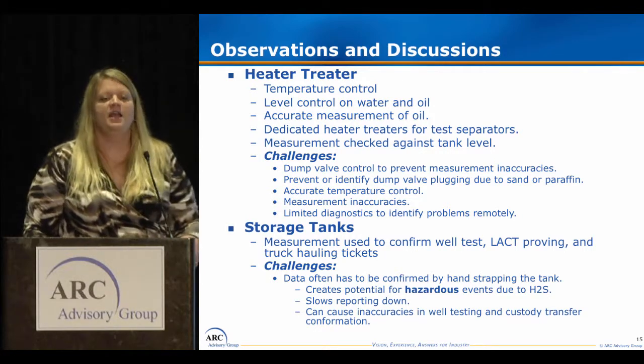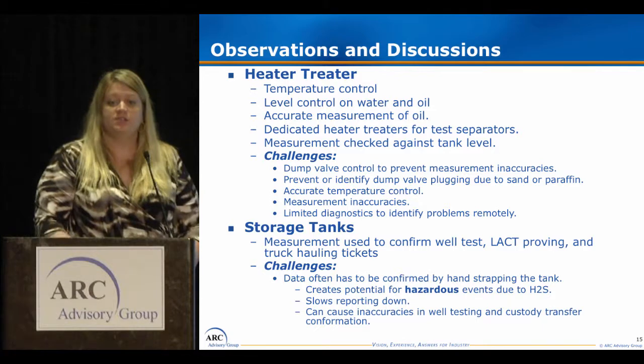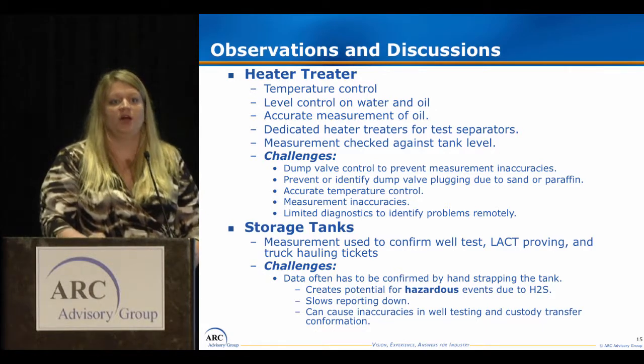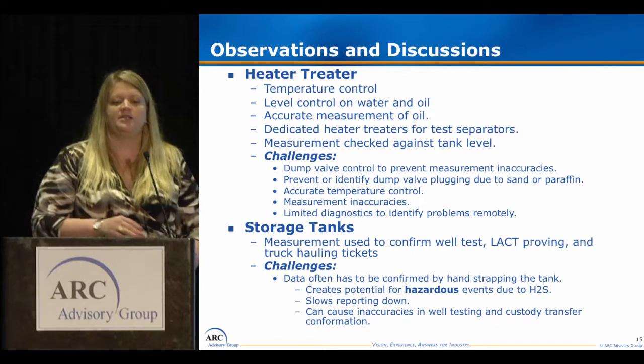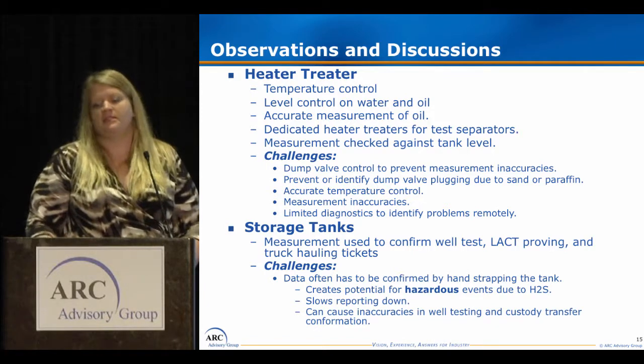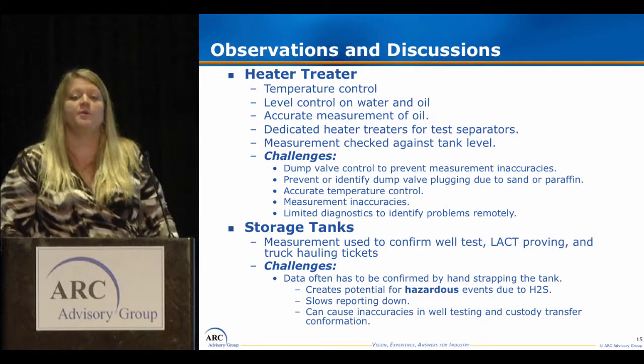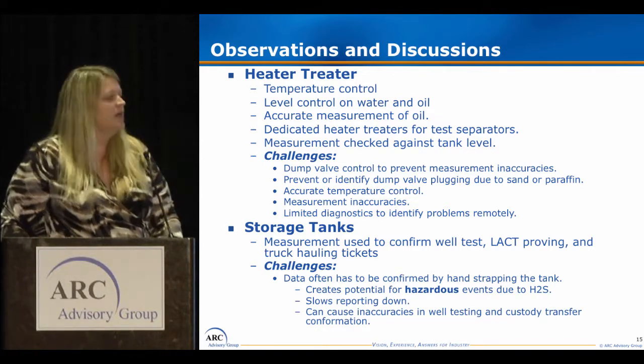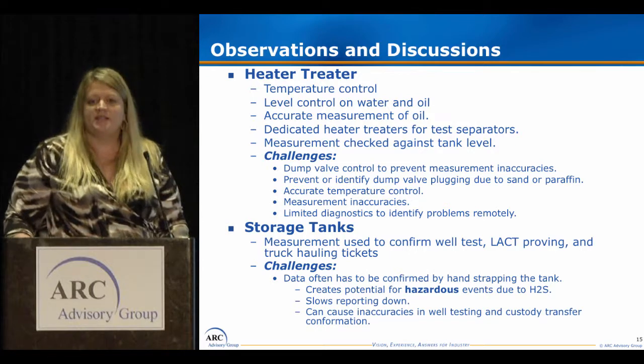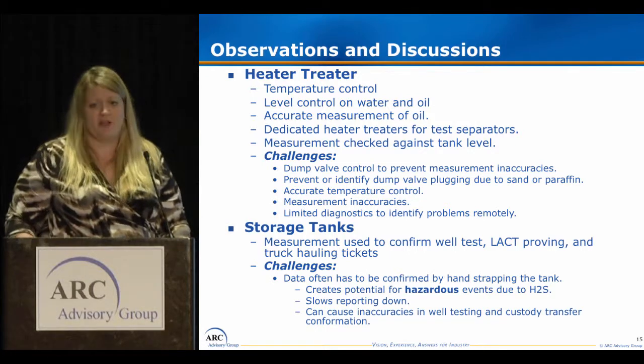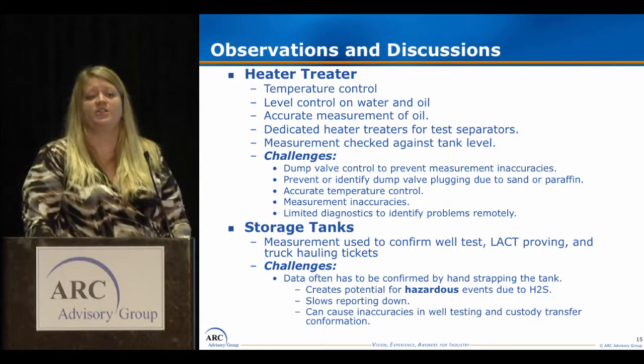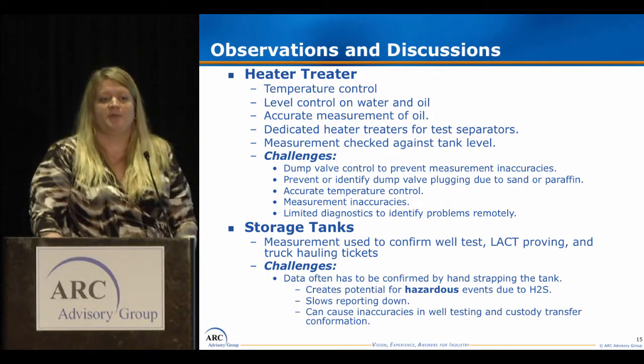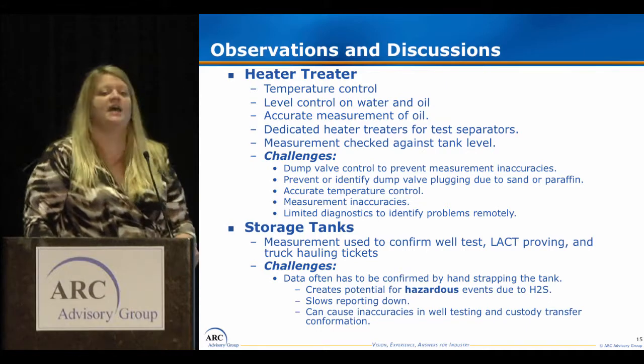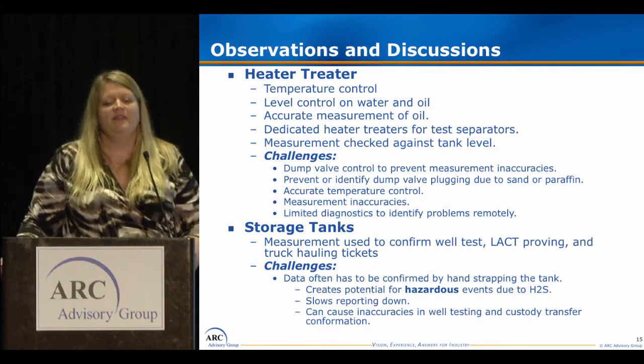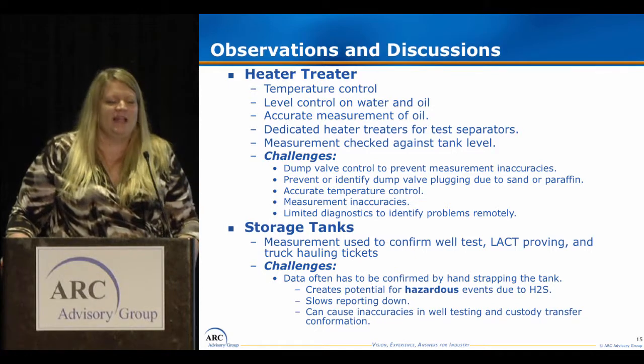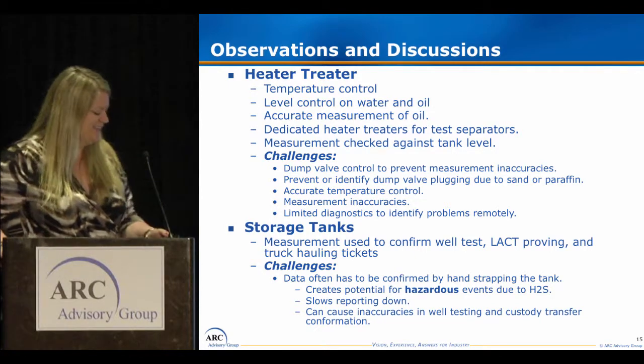A big thing, and the first thing I focused on, was gauging the tanks. I don't want any manned personnel manually gauging tanks, because in Eagle Ford we have high H2S. In Mississippi it's not so much a problem, but we're pretty remote, and you're out there by yourself. So unless something is wrong with the SCADA equipment or RTU, which is very unlikely, the RTU data is still there, and they don't need to be on top of the tanks gauging. That was a pretty easy transition, and they were mostly thankful, though I guess they did like climbing up those tanks to gauge them sometimes.